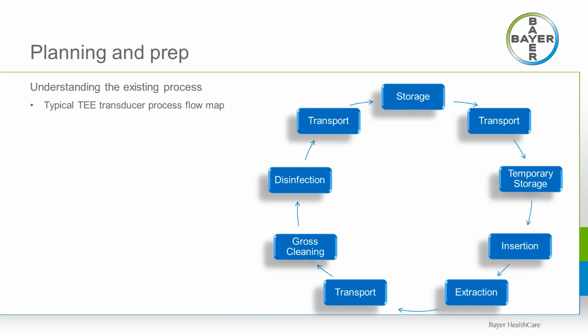So, once the gross material is removed and the probe is wiped down, then it's taken to be disinfected via submersion. So there are several methods of disinfection, ranging from soaking in a bin or a basin to immersion in a tube system or placement within an automatic disinfection machine. There's really no method which is more effective than another. The differences between the different processes really present themselves through efficiencies and ease of use.